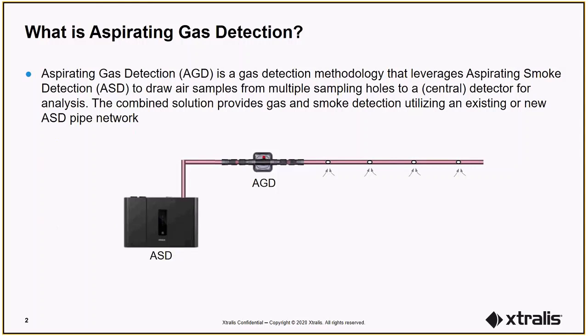An aspirated gas detection system leverages the ASD pipe network to transport air from multiple sample points to the gas detector for analysis of gas threats. What aspirating gas detection offers is a simple addition to the ASD system. Now gas detection is accomplished in parallel to smoke detection. Also, with the aspirated and multi-point sampling methodology, significant cost savings can be realized on installation, service, and maintenance activities.